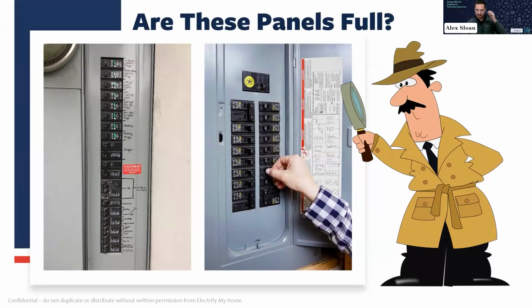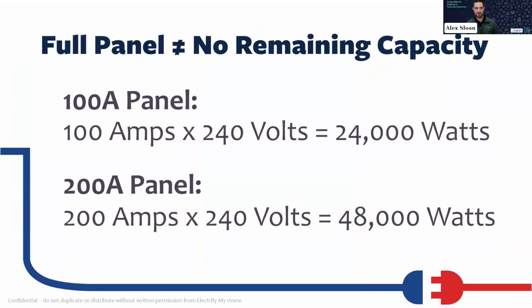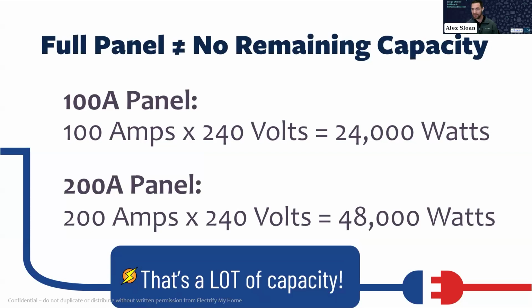As we look at typical residential electrical panels, you might see something like this and ask, are these panels full? We get questions from homeowners all the time saying there's no more slots available in my panel, what do I do? Having a full panel in terms of no space doesn't necessarily mean there's no remaining capacity. On a typical 100 amp panel, we actually have 24,000 watts, and on a 200 amp panel, 48,000 watts to work with - that's a lot of capacity.